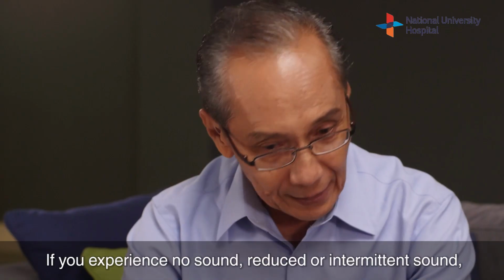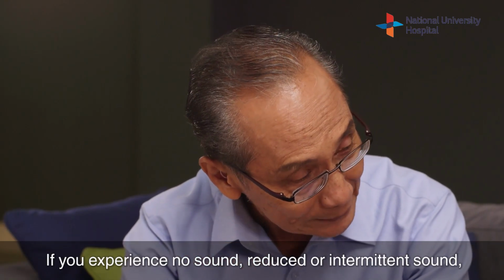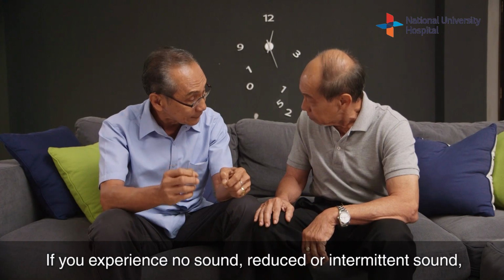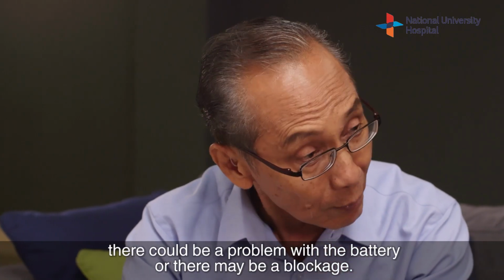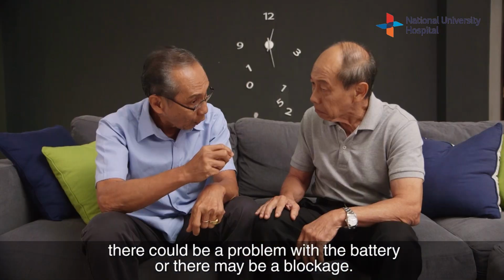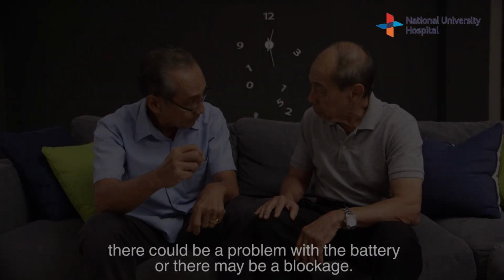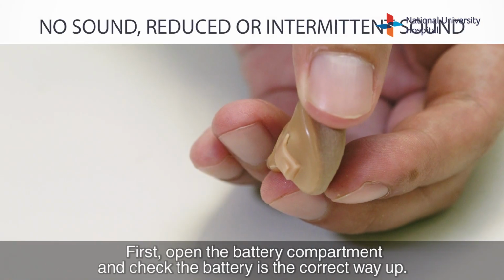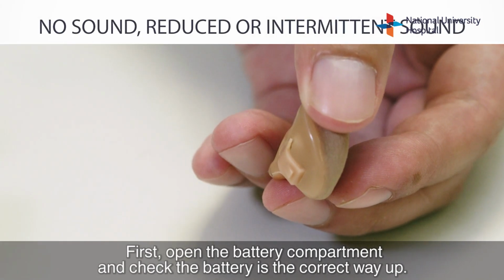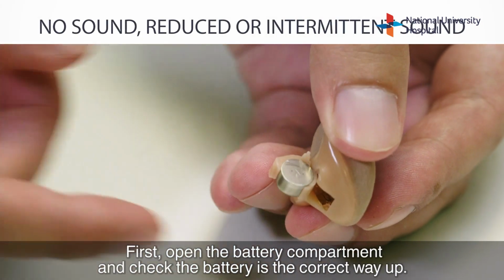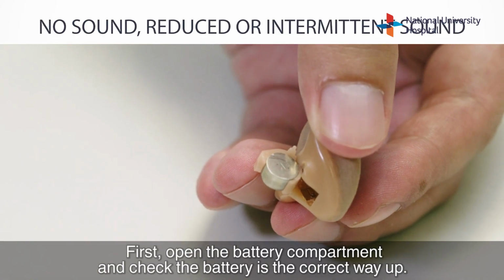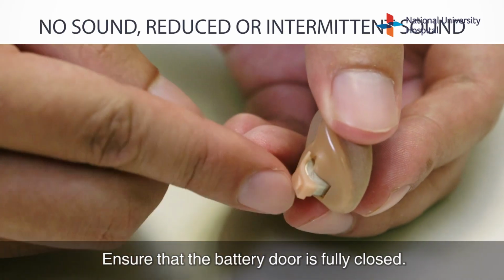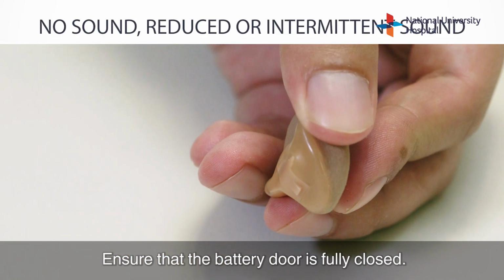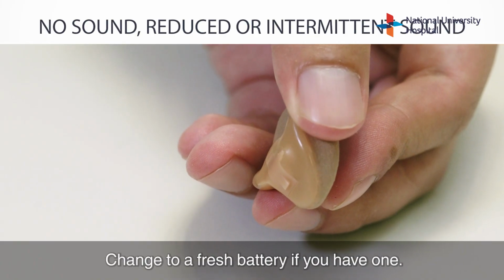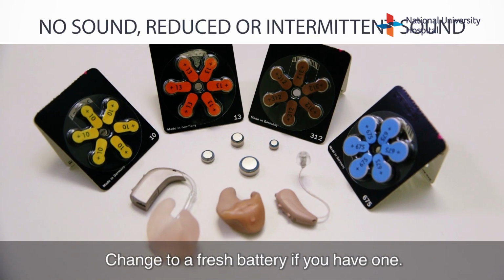Okay. If you experience no sound, reduced or intermittent sound, there could be a problem with the battery or there may be a blockage. First, open the battery compartment and check the battery is the correct way up. Ensure that the battery door is fully closed. Change to a fresh battery if you have one.